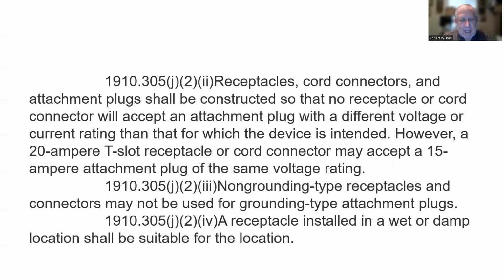Receptacles, cord connectors, and attachment plugs shall be constructed so that no receptacle or cord connector will accept an attachment plug with a different voltage or current rating than that for which the device is intended. However, a 20 amp T-slot receptacle or cord connector may accept a 15 ampere attachment plug of the same voltage rating. Non-grounding type receptacles and connectors may not be used for grounding type attachment plugs. A receptacle installed in a wet or damp location shall be suitable for the location.